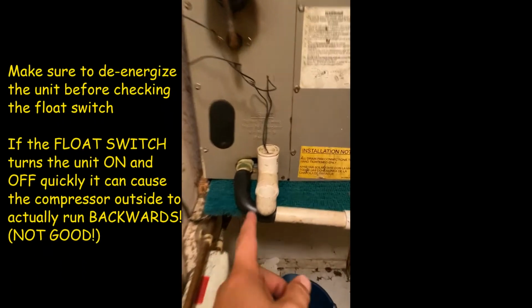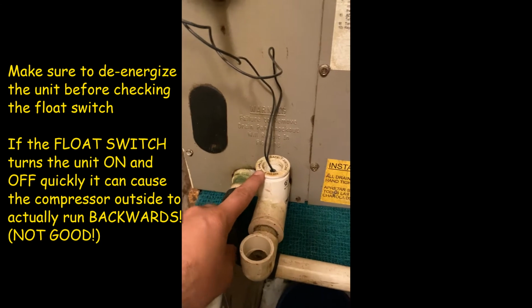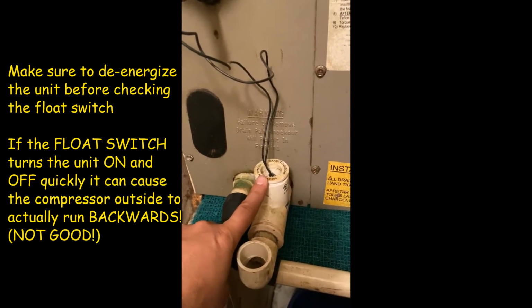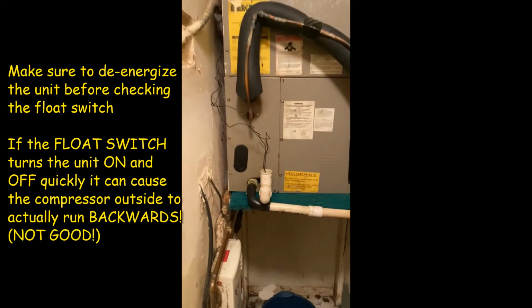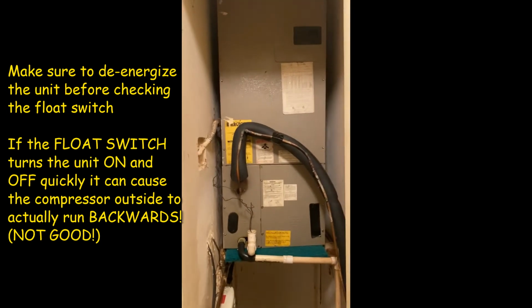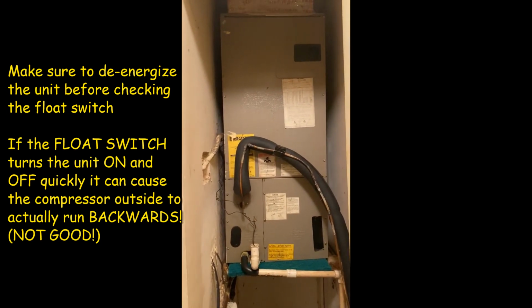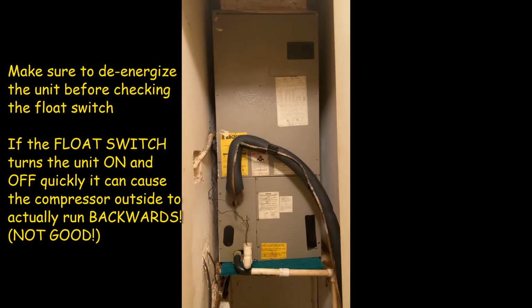You should always turn your unit off when taking this out, okay? Because it can cause a problem. If you turn it on and off quickly, it can cause an issue outside. Okay, so if it's not our safety breaking our control voltage, then we have to open the panel and start looking inside. Most units will have a service disconnect or a breaker on the air handler itself so that you can de-energize the unit before you start messing with anything in there. So that's the first thing you're gonna do, is de-energize the unit. That's where your power comes in.